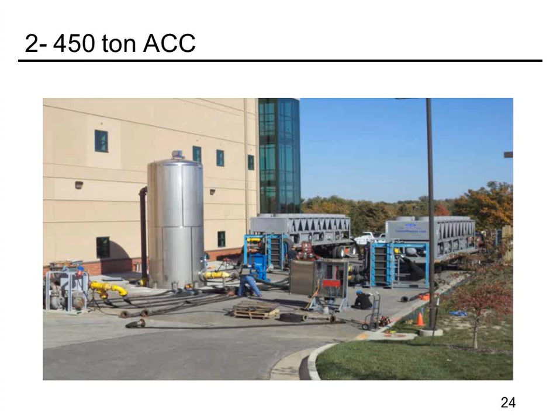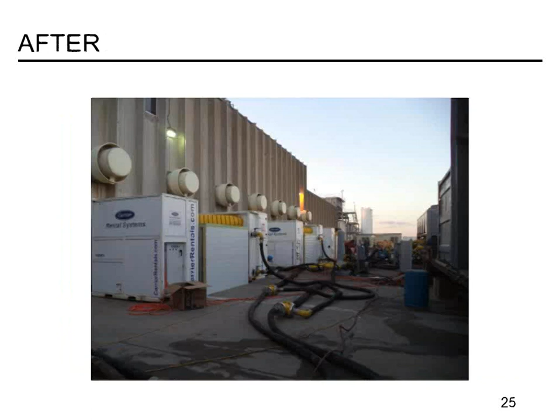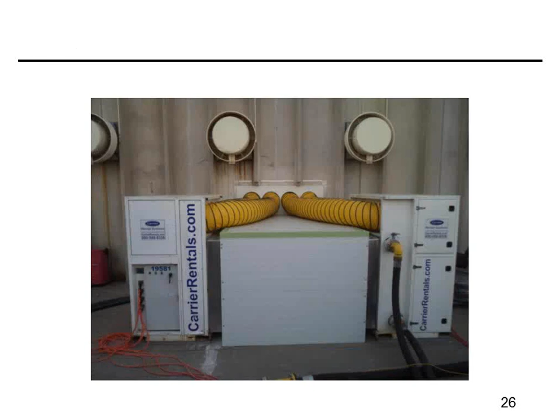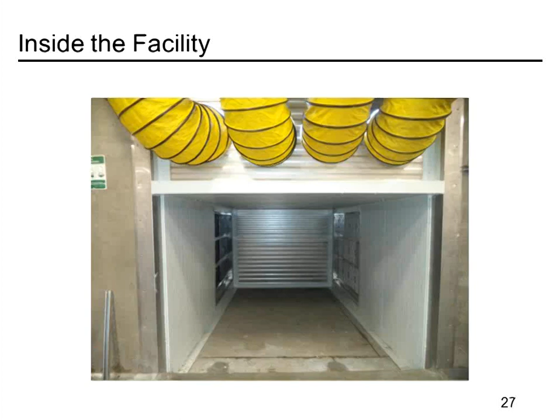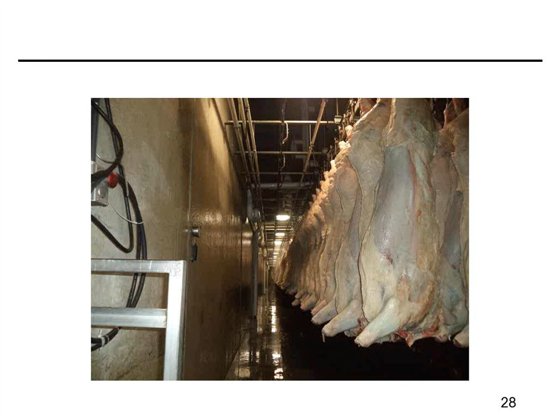Here's a different job showing a courtyard that we turned into a bit of a mechanical room. We have a bunch of air handlers. There was no space within the facility. This is a meat packing plant, and these are air handlers that are controlling the temperature of the space to be 40 degrees. We're doing lots of air exchanges in there because of the nature of the project and the meat packing plant. You can see these are custom-made plenums with our units sitting outside, so we're pulling the air in through it at 40 degrees, and returning it to the space. And as I mentioned, you can see it's for a meat packing plant.